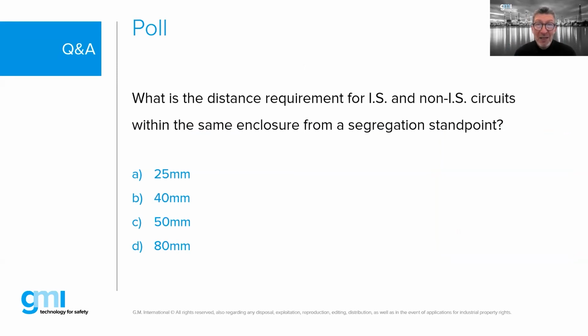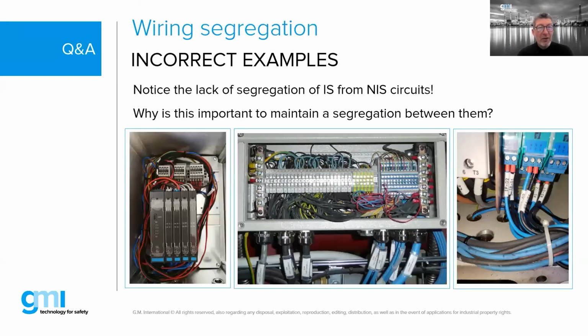It's 50 mm. And here are some examples of incorrect, I guess, wrong segregation, no? Yeah. On the left-hand side, where we see service loops on the inside of a panel, that is a big no-no. Obviously, in the picture in the middle, where we have some IS on the right-hand side and non-IS, that's a big issue. We have a separation on the right-hand side with those intrinsically safe barriers, but the problem is that all of a sudden the cabling was run to entries right next to power conductors. So we violated our 50 mil separation.